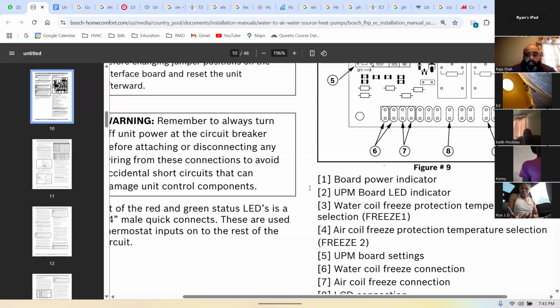Okay? In cooling, you might jump out some things. In heating, you never jump out anything and leave the room. Never jump out anything in heating and leave that room under any situation or circumstance. You could burn that building down. Even with just bypassing safeties for testing, I've almost burnt down units before. So be very careful.